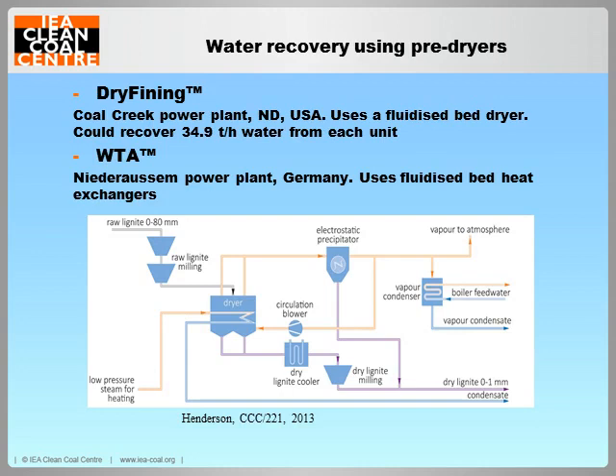Commercial systems are available that pre-dry the coal and capture the evaporated moisture before it is pulverised. Two of these are the DryFining and WTA systems. The DryFining system is installed at the Coal Creek station in the USA. It uses a fluidised bed dryer to dry the lignite. Evaporated moisture is currently vented to the atmosphere, but if you installed water-cooled condensing heat exchangers, these could capture nearly 35 metric tonnes per hour of water from each unit.